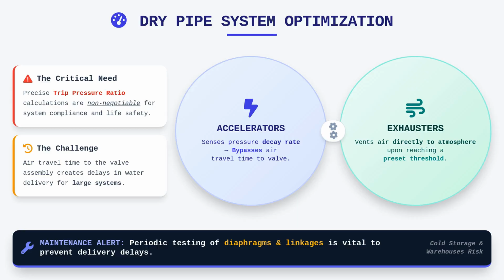Exhausters provide a similar function, but work by venting the air directly to the atmosphere once a preset pressure threshold is reached. These devices are mechanical in nature, but they require periodic testing to ensure diaphragms and linkages remain responsive under long-term conditions. Failure to maintain these components can lead to a significant increase in the water delivery time, potentially compromising life safety objectives in large warehouse or cold storage occupancies.